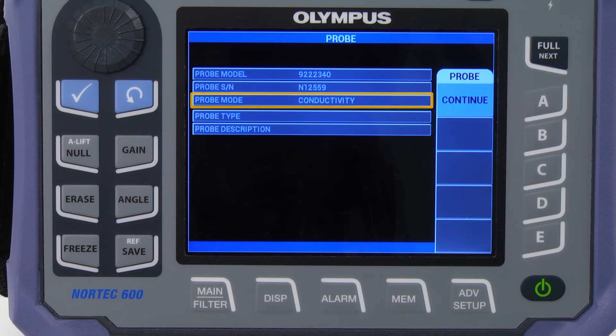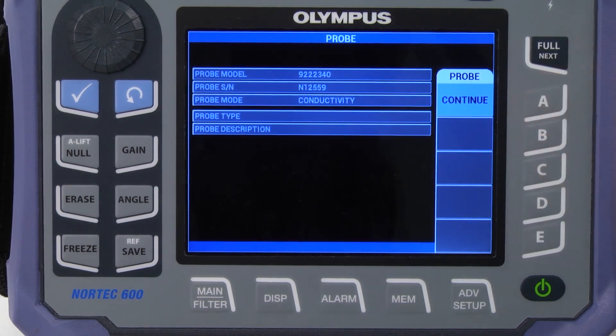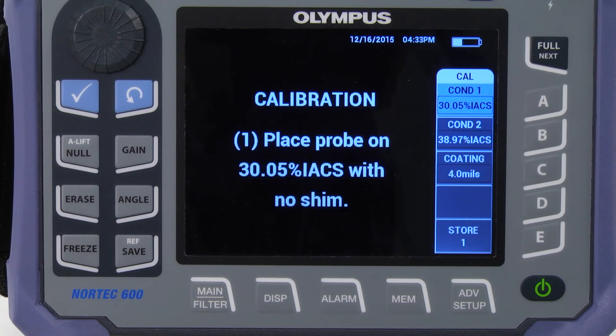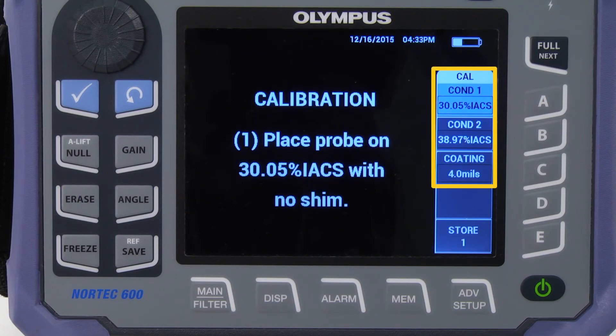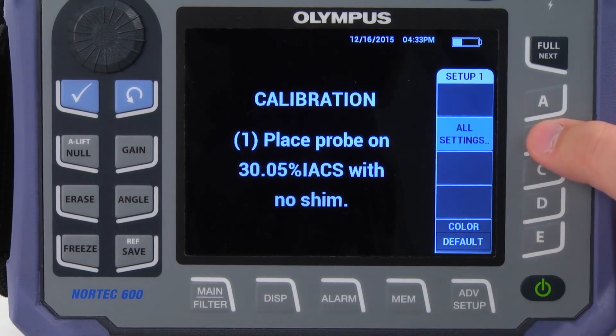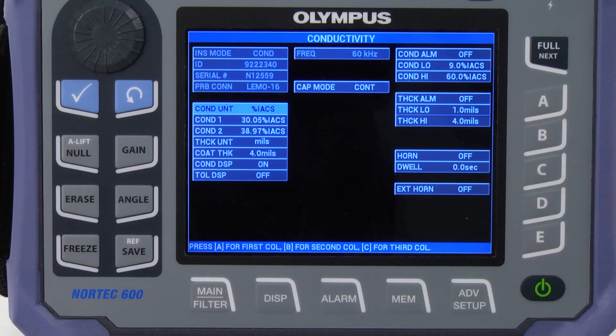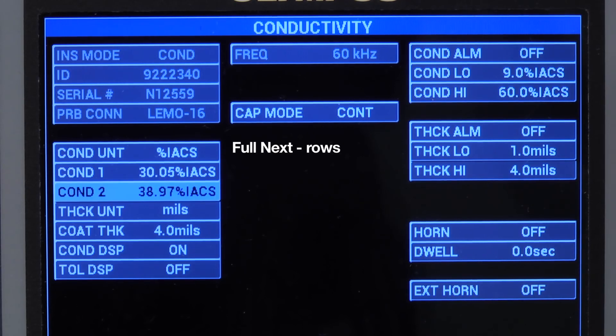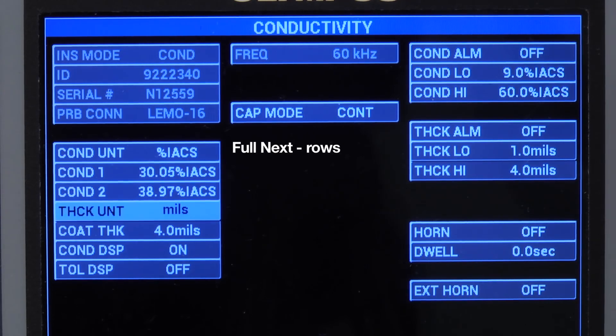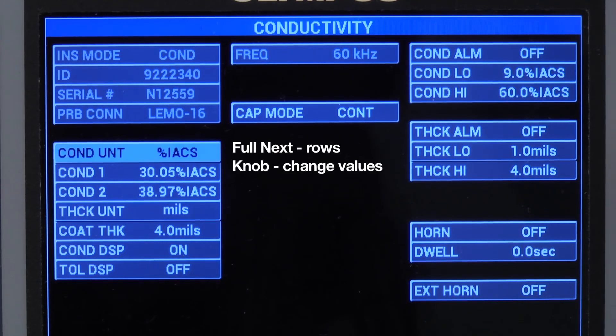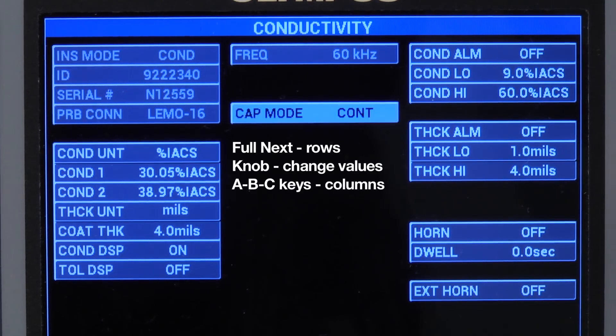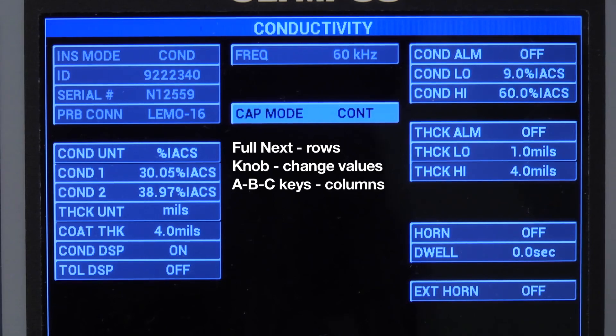Press Continue. In this example, we are using IACS and mils units because of our calibration standard. To change the units, press the Advanced Setup and the All Settings key. Use the Full Next key to navigate the rows, the knob to change the values, and the ABC keys to change columns.